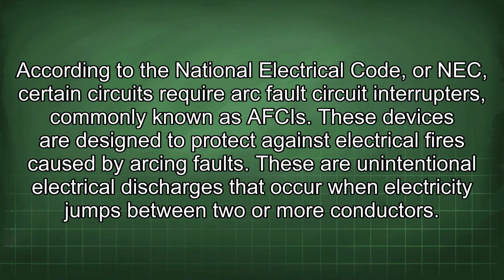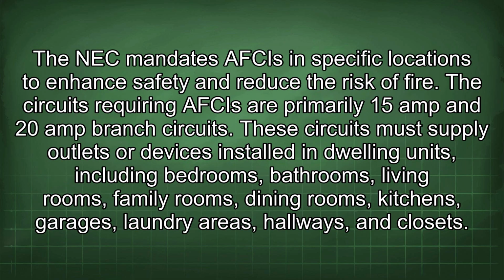According to the National Electrical Code, or NEC, certain circuits require arc fault circuit interrupters, commonly known as AFCIs. These devices are designed to protect against electrical fires caused by arcing faults. These are unintentional electrical discharges that occur when electricity jumps between two or more conductors. The NEC mandates AFCIs in specific locations to enhance safety and reduce the risk of fire.